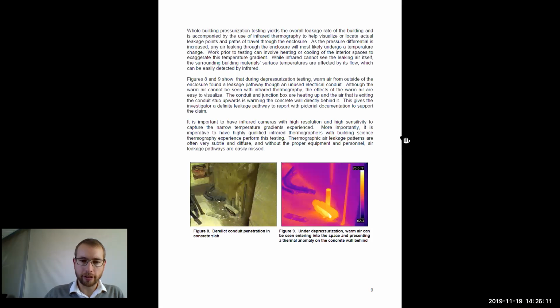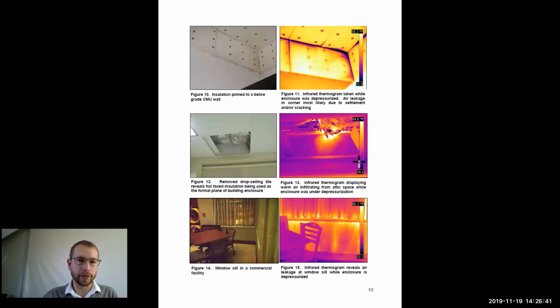Let's see, and go down to the next page. So he really notes the importance of having a finely tuned camera specifically focused on small areas at a time, so you get a very narrow temperature range to really highlight areas of infiltration. And what you want to be looking for are basically these streaks, if you will, where air is actually coming through. And he likes to run it on a depressurized building, if possible. So you're basically reversing the airflow and trying to exhaust more and pull air in, the opposite of what a building's normally doing, but it really highlights points of infiltration if the building operator is willing to do that. So here you can see some infiltration that's happening around the insulation that's been pinned to a masonry wall construction.